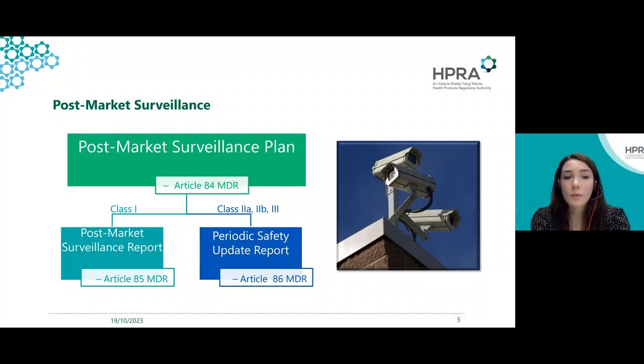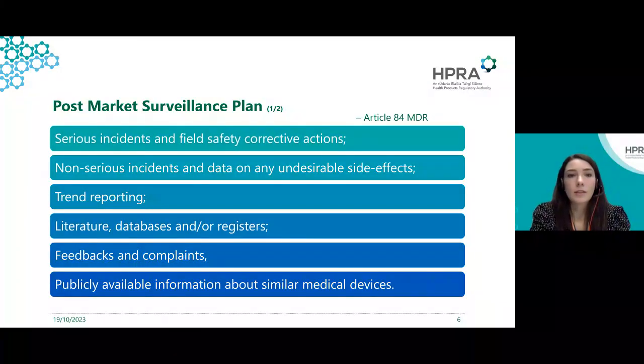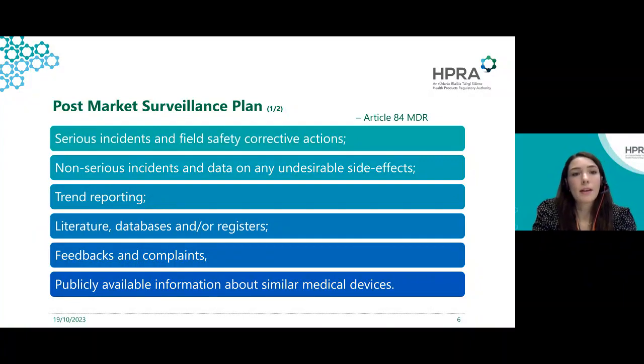For Class 2A, 2B and 3 devices, manufacturers must compile a Periodic Safety Update Report. The legislation is more prescriptive in what the PSUR or Periodic Safety Update Report should contain and how frequently it needs to be updated. So this is every 1 to 2 years, depending on the risk class of the device. So now just to explain the post-market surveillance plan in a little more detail.